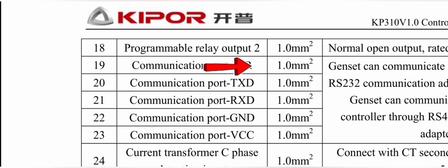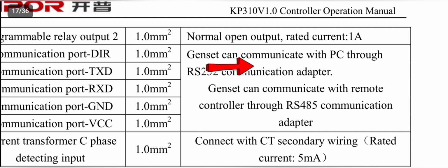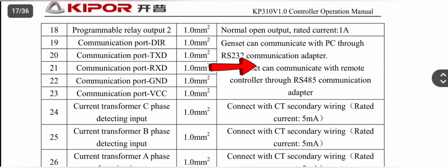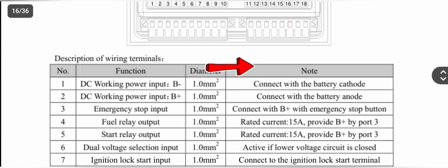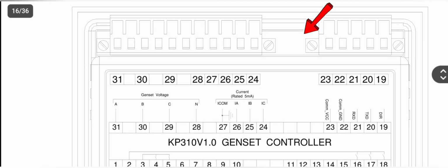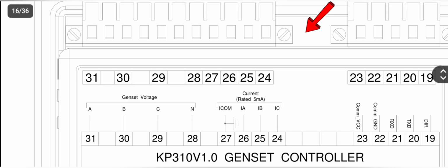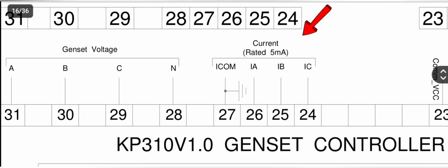Okay, the communication port is used so the genset can be communicated with the PC through the RS-232 communication adapter. The genset can be communicated with a remote controller through the RS-485 communication adapter. This is used to program your controller through the PC. After that, pins number 28, 27, 26, 25 and 24. 27 is the ampere common. Current rated at 5 amperes.